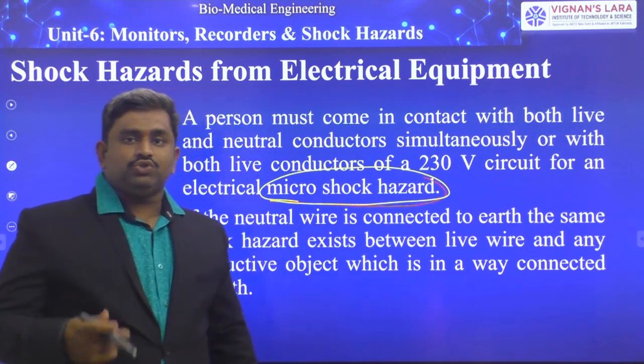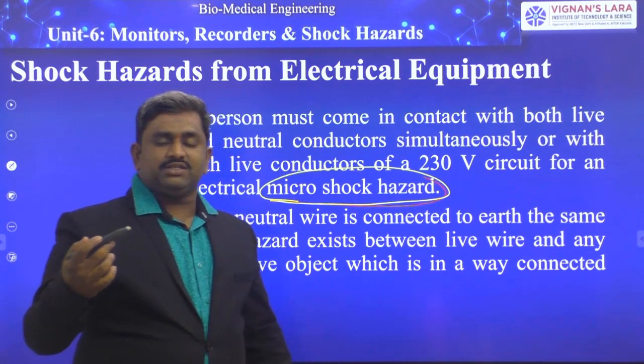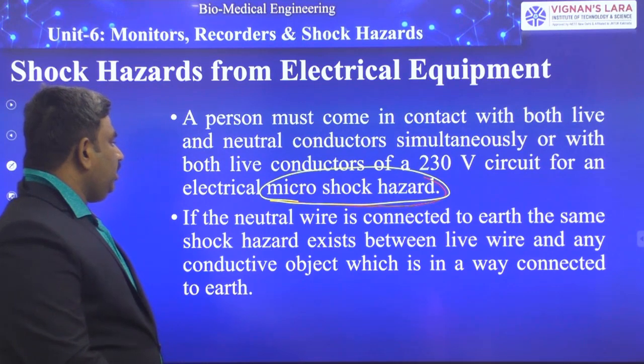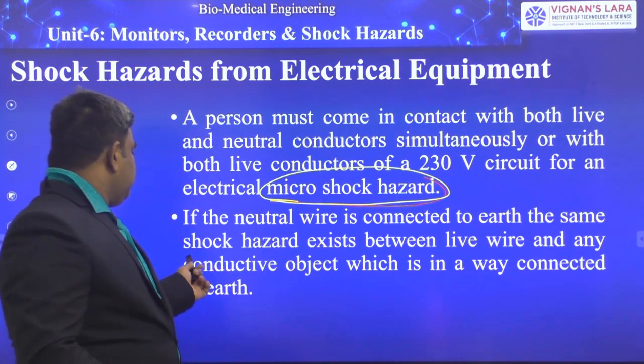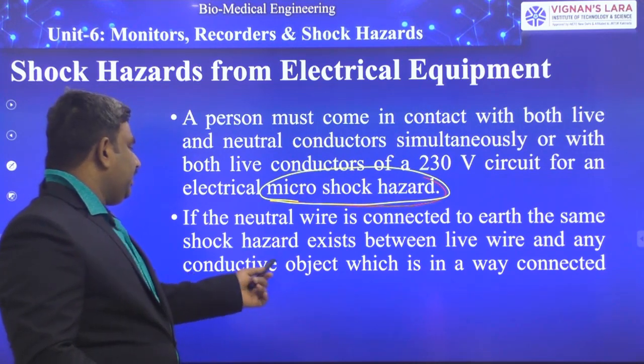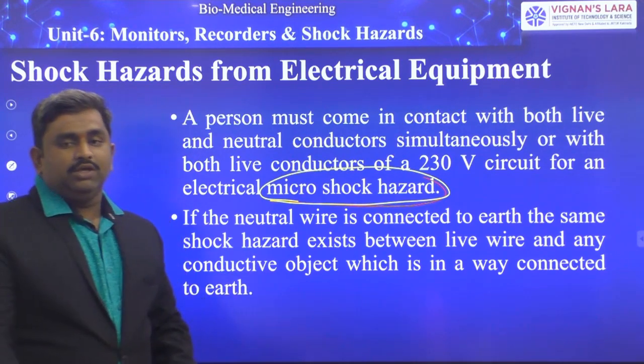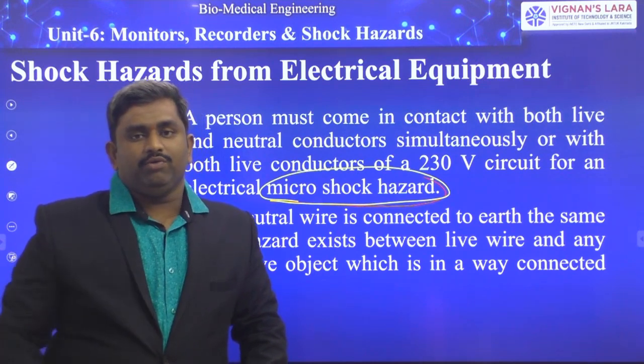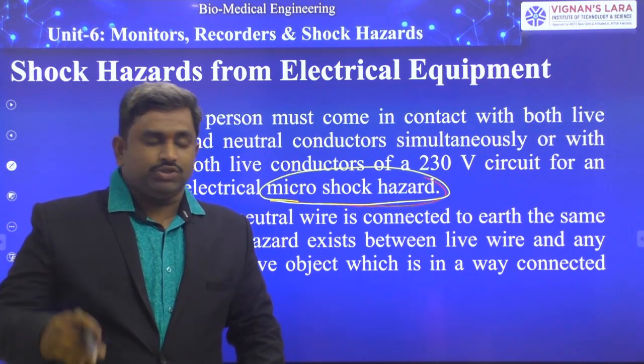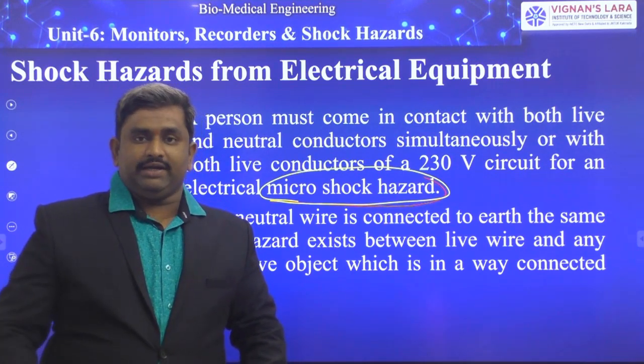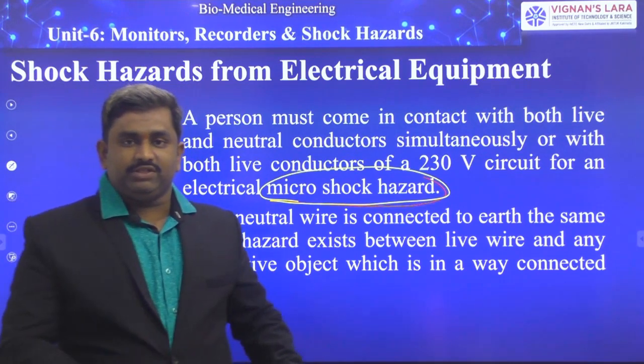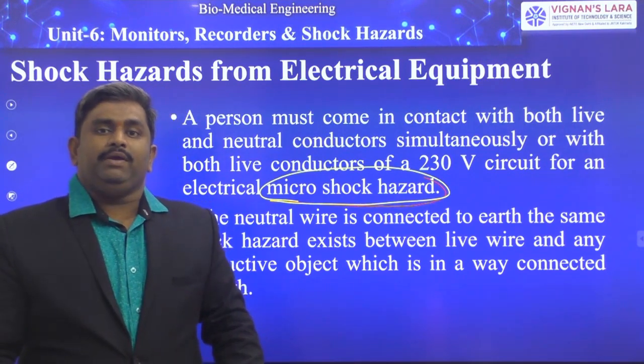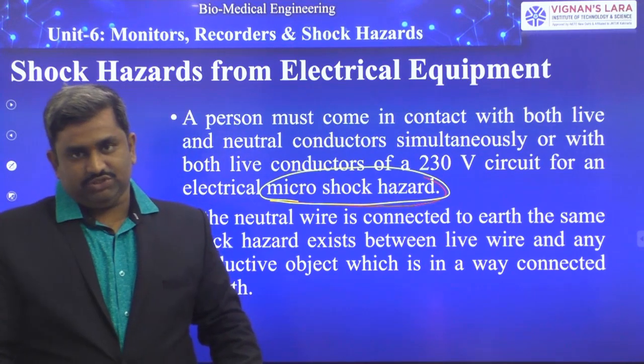For microshock, one conductor comes into contact internally with the body. If the neutral wire is connected to earth, the same shock hazard exists between the live wire and any conductive object connected to earth. So wherever the neutral wire is connected to ground, if the human body or conductor comes into contact with that neutral wire, the shock will happen to the patient's body.